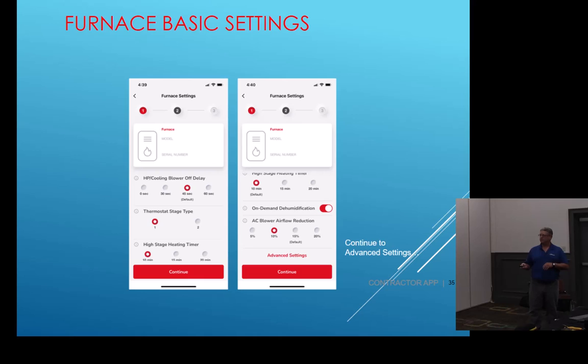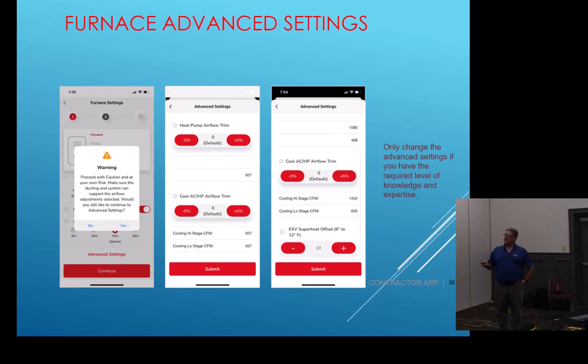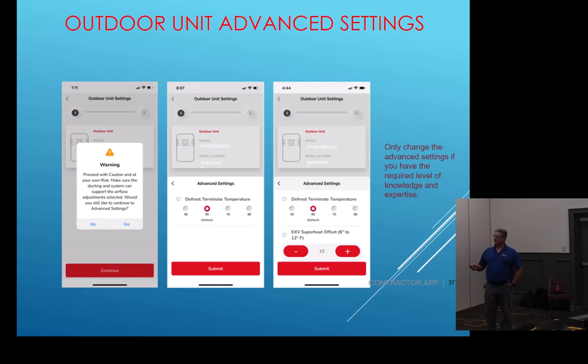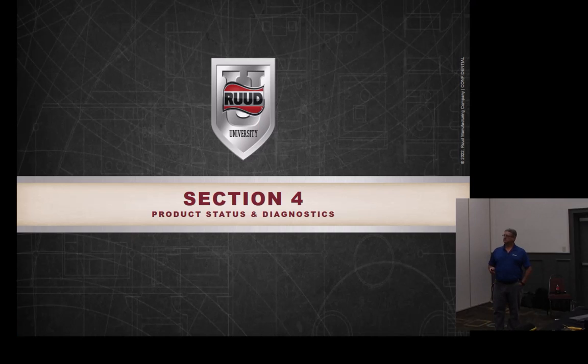Change that setting, okay? When you do change these settings, I want to mention, if you go up 5 or 10% here, it gives you a CFM number. It will show you what you changed it to. It will show you the increase, so you'll know how much CFM you're dealing with, okay? We talked about our defrost termination. You can come in here and change it. I think probably 60 on the default is probably good for our areas.